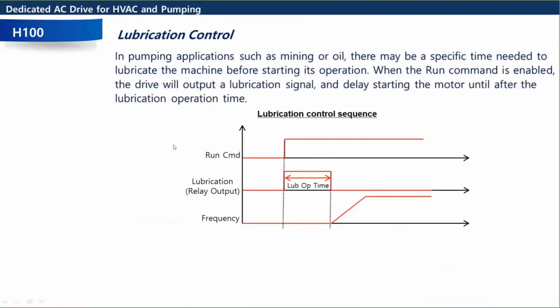And we also have the lubrication control. So this is lubrication for a pump that's going to need to be pre-lubed. Okay, so if you program a relay output for lubrication, when you give the drive a run command, it's going to pre-lube the motor, and you can set the time it's going to take to lube up that motor. So very easy thing to set up, just a couple of parameters like a time and a relay output.